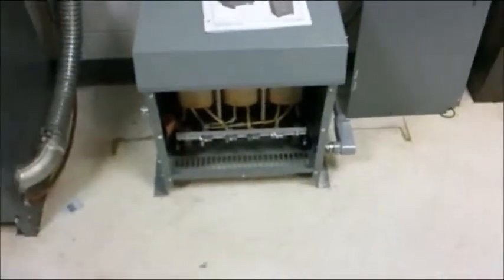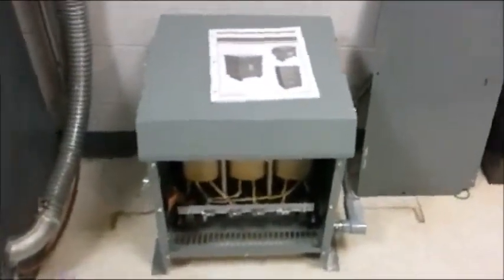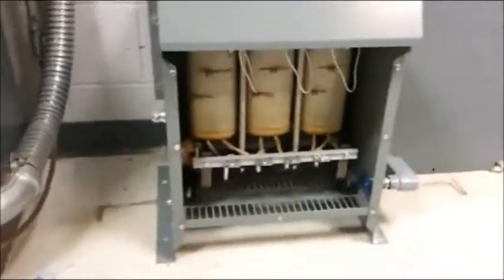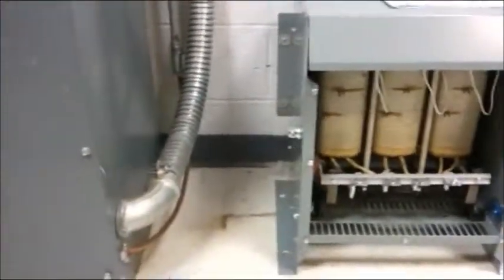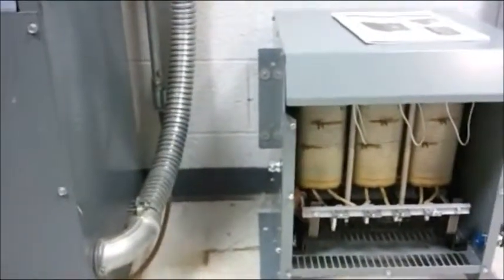Okay, again, here's the wires that go up, and what they do is they feed two transformers over here, which in turn feeds these panels over here. And what we're going to do is come up with a 1/2 inch conduit right up in here, come out, and we're going to follow right along the wall line, and we're going to come down, and here's a transformer that I installed the other day. It's only a 15 kVA, which is about 50 amps, and we're going to come down right there in between the two transformers with 1/2 inch conduit, and that's going to be our line side that feeds the transformer.